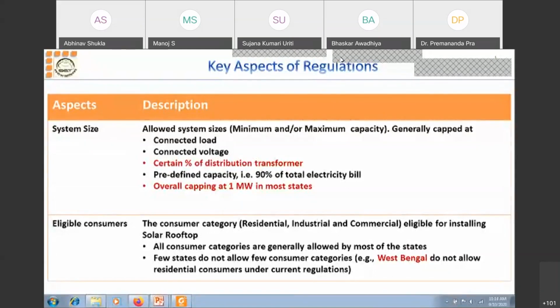If you have any contact, you can say that the size does not matter, because it is working on mutual induction. So whether the solar plant is a bigger or smaller size, the capacity does not matter. How much your transformer is loaded, whether at 100%, 80%, or 200% load - if it is 200% load, you can allow 200% of solar plants, but you have to do some study. On behalf of these distribution companies, educational institutes can do some study and research work.